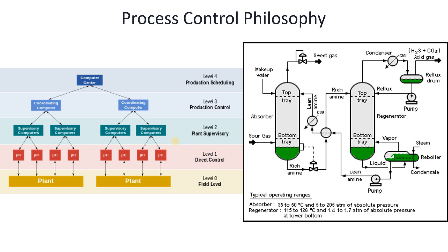For example, here is a pump connected to a kettle-type reboiler. If the kettle-type reboiler level goes low-low, an interlock must be provided so that the pump trips. If the pump is not tripped, the pump's internal parts could be damaged and cavitation could occur.